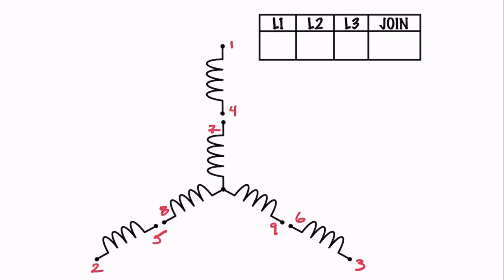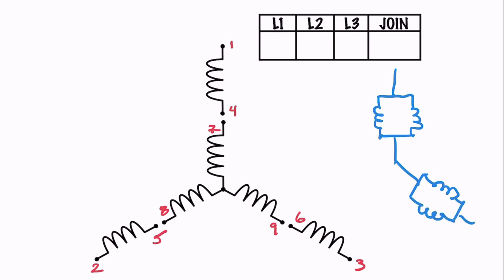What I like to do is have students draw it out since they're very familiar with how these loads work. We have one set of windings, and 120 degrees apart another set, and another 120 degrees away the third set. Starting at the top: I've got leads one and four for that winding, and I'm going to connect four to seven, then seven goes to the internal star point — the phantom lead. I'm not going to draw the 10, 11, 12 leads; I'll just leave those out.